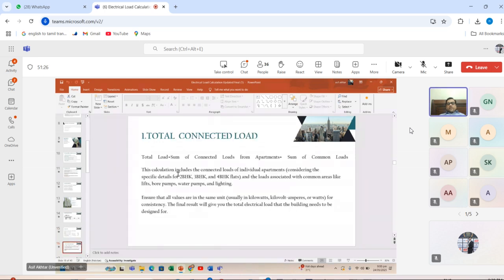This calculation includes the connected load of individual apartments, considering the specific details for 2 BHK, 3 BHK, and 4 BHK flats, and the load associated with the common areas like lifts, bore pumps, water pumps and lighting. So there are two types of loads involved in this calculation: one is for apartments and one is for common loads. Ensure that all values are in the same unit, usually kilovolt amperes or watts, for accuracy. The result will give you the total electrical load that the building needs to be designed for.